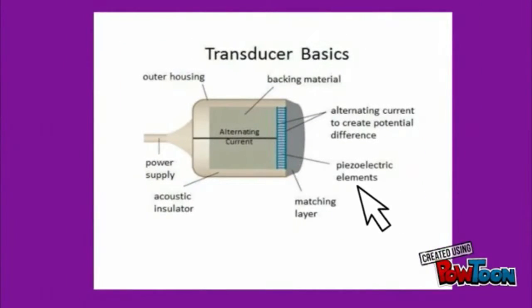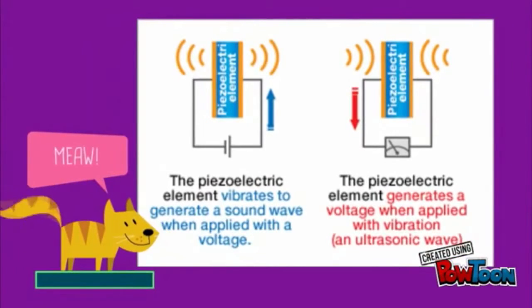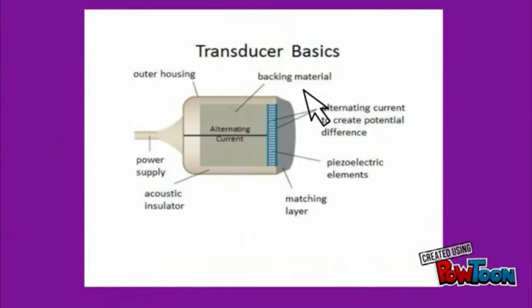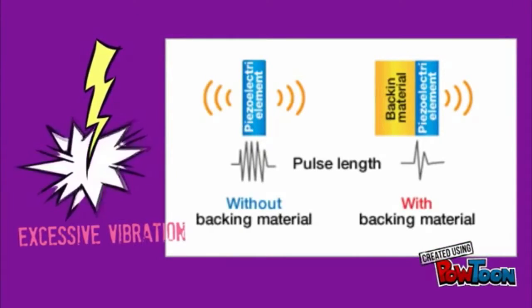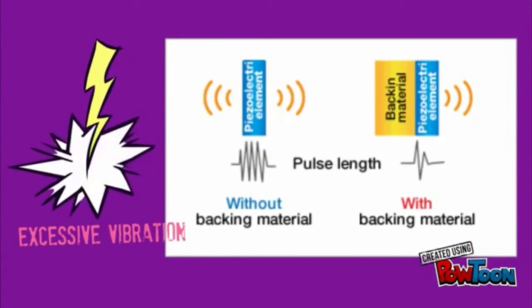Components of a transducer: first, the piezoelectric element, which vibrates to generate a sound wave when a voltage is applied. Second, the backing material, which is used to prevent excessive vibration, generating an ultrasound wave with a shorter pulse length.